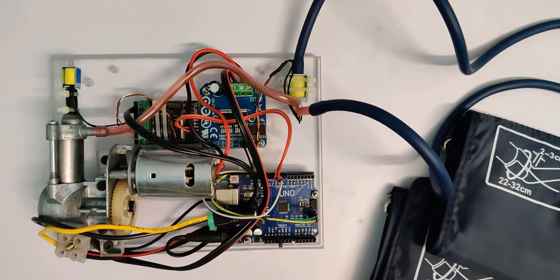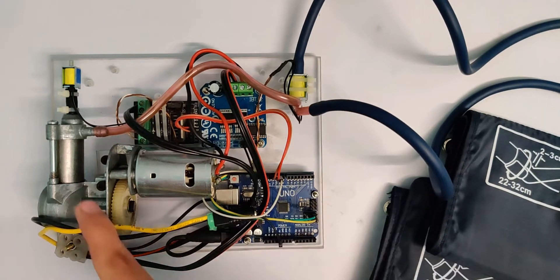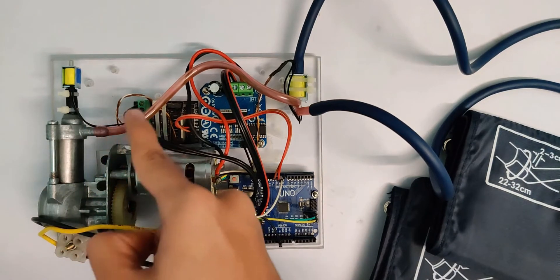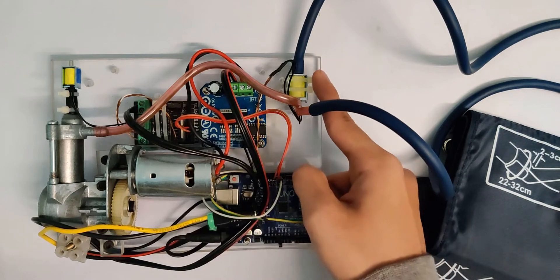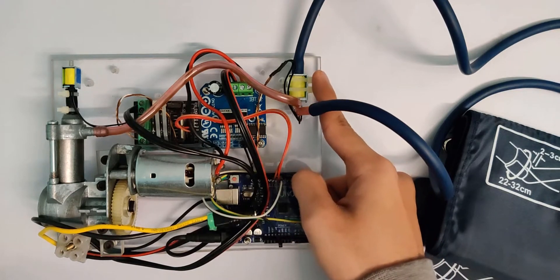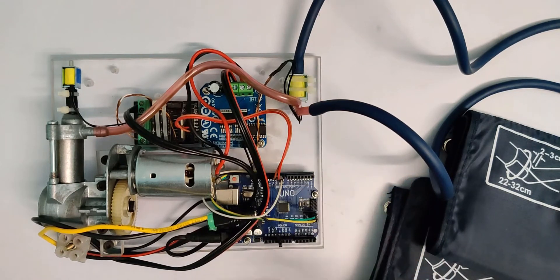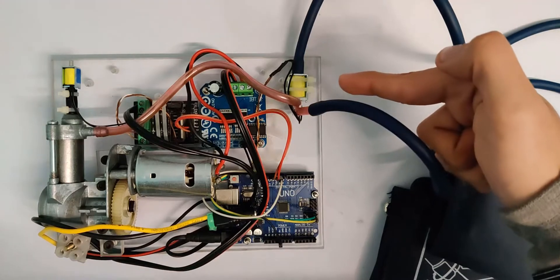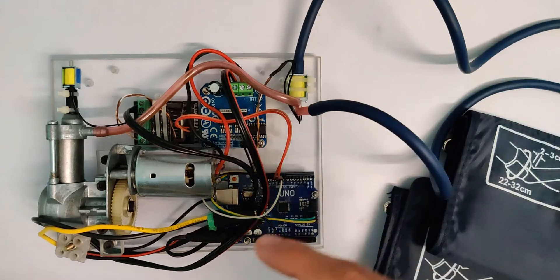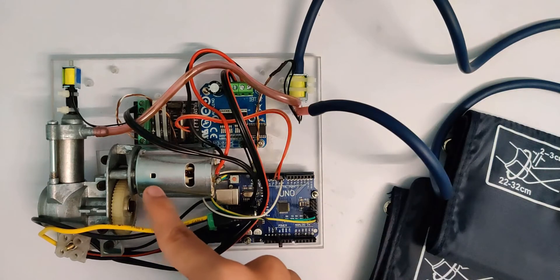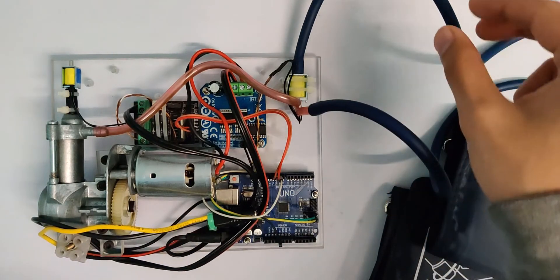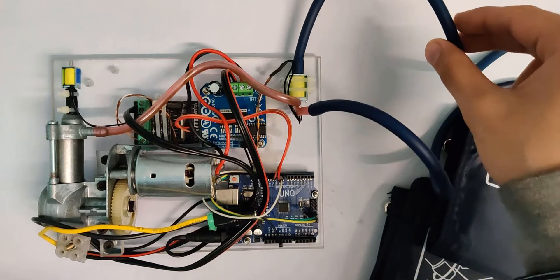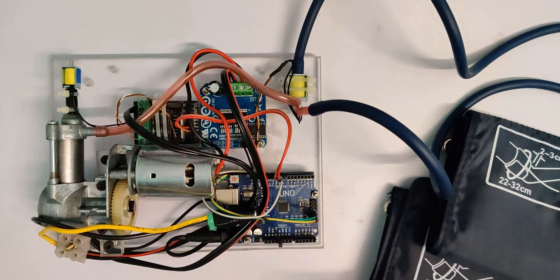And on the other outlet which goes here to this two-way three-position valve. You can call it a splitter in other words. This splitter directs the pressurized air from this pump to the desired cuffs so that they can inflate the way you want.